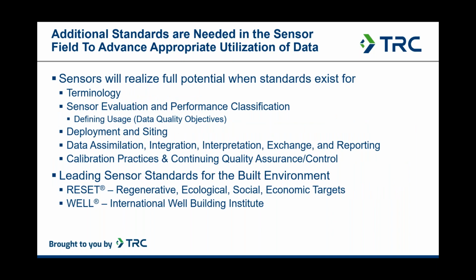But we still have a long way to go across the sensor spectrum to see that they enjoy the full benefits. We need standards that address terminology, the full range of sensor evaluation and performance classifications, how to properly deploy and site these, how to acquire, process, and report the data, and then really an important area is what are the continuing practices for ongoing quality assurance and calibrating these devices. Once we have those standards fleshed out, we'll really see sensors achieve their full potential.